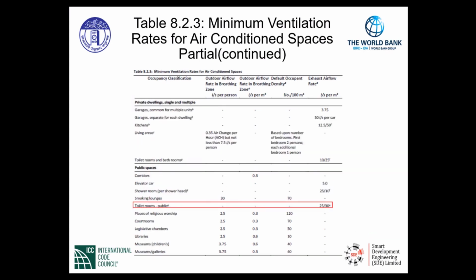Another category that must not be forgotten in our commercial buildings is public spaces. As you can see, some of the areas and locations in public spaces range from corridors to elevator cars, shower rooms, smoking lounges, toilet rooms, places of religious worship, courtrooms, etc. When we look into the public spaces category a little closer, for example, toilet rooms, public. After the word public, there is a note G. Note G refers the code user to the notes of the table. There's specific information about recirculation of that air regarding public toilet rooms. So we'll want to go take a look at note G of the table.